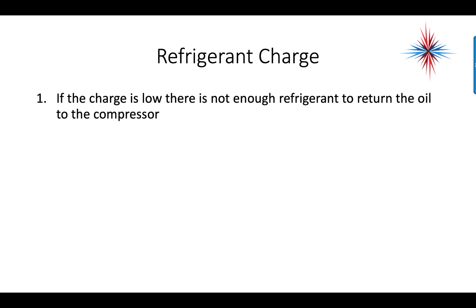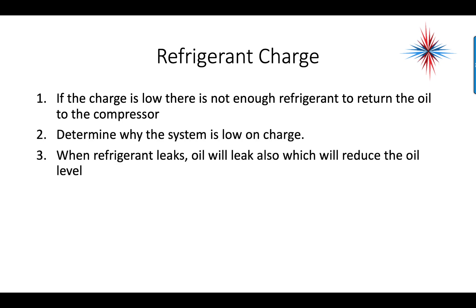If the charge is low, there's not enough refrigerant to return the oil to the compressor. Determine why the system is low on charge. When refrigerant leaks, oil will also leak, which will reduce the oil level. Remember, one of the premier ways to find leaks in a refrigeration system is to look for the oil.